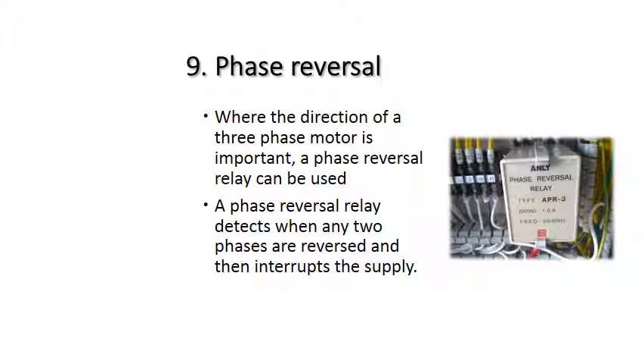Next is phase reversal, and it's important that a motor goes the right way. In particular, for a three-phase motor, you might want to use a phase reversal relay. Why would you need one of these? You've probably covered three-phase motors by now and know that it is really easy to make them go the wrong way or change direction. All you have to do is change over two phases.